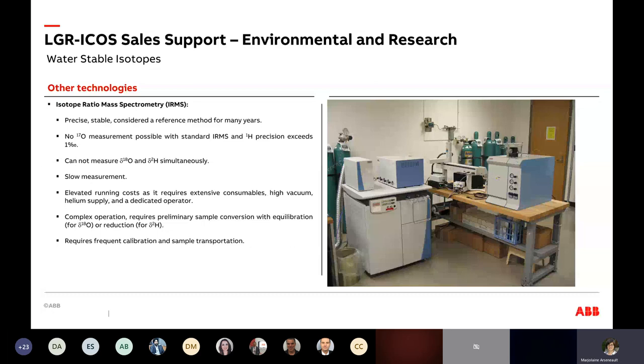Just another word on mass spectrometry: they may not be seen as a competitor. Our technology could be combined and be in addition to a lab already equipped with mass spectrometry. An injection takes about 90 seconds, while a reading with mass spectrometry takes minutes. So you can see ICOS as a screening tool. We know it's not a gold standard but it is commonly used as a standard. Also, mass spectrometry can only read one measurement at a time — O-18 and deuterium cannot be read simultaneously — which is possible with ICOS.